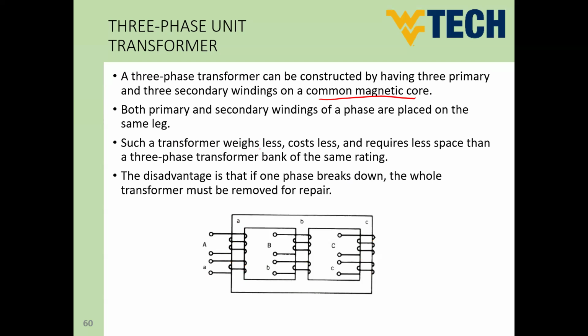Such a transformer weighs less, costs less, and requires less space than a three-phase transformer bank. Why? Because by the end you will have just a single unit. You don't have three units and connections between them. So by the end you will have just one circuit. And also, it would have less magnetic material compared to the three single-phase transformers.